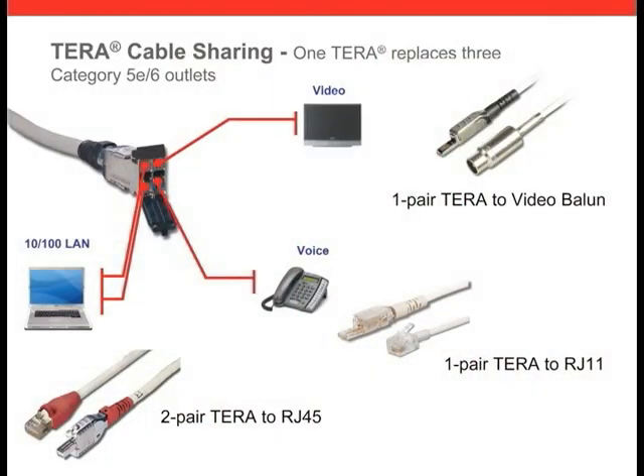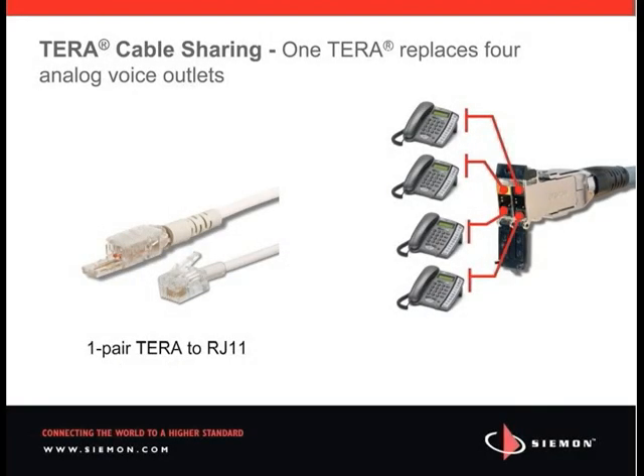Siemon's fully shielded TERA cabling can also uniquely support up to 4 separate applications with just one cable and outlet. This practice is called cable sharing. Fitting within a standard RJ45 footprint, the combination of the TERA outlet and cord options allows extremely simple facilitation of cable sharing. As with traditional cabling channels, all 4 pairs of each cable would be terminated in a single outlet.